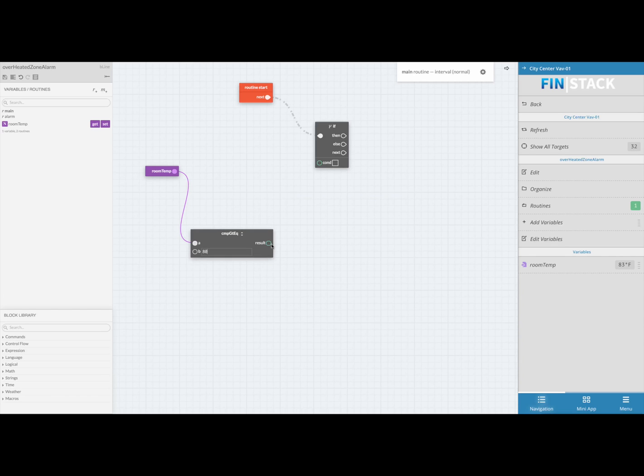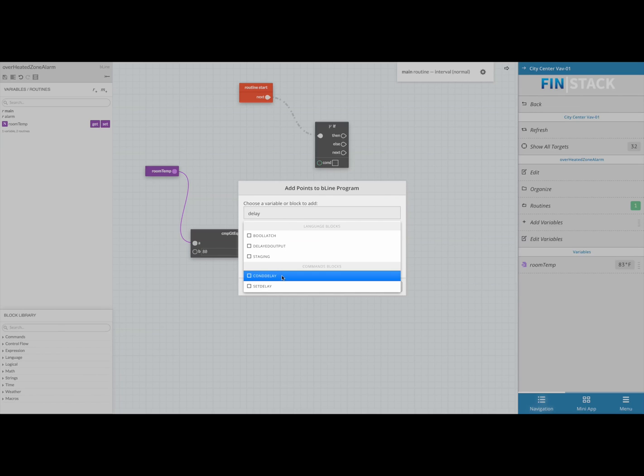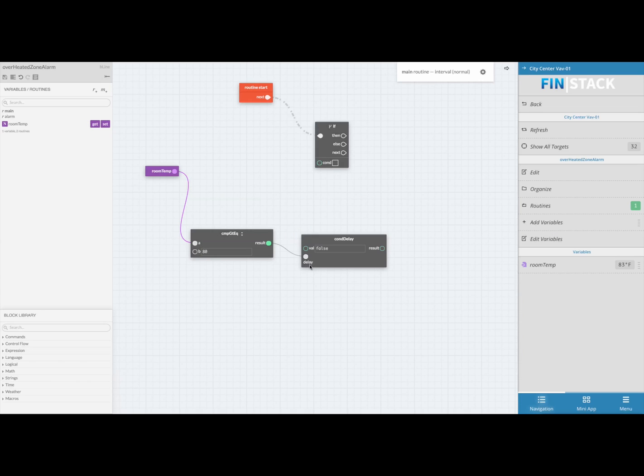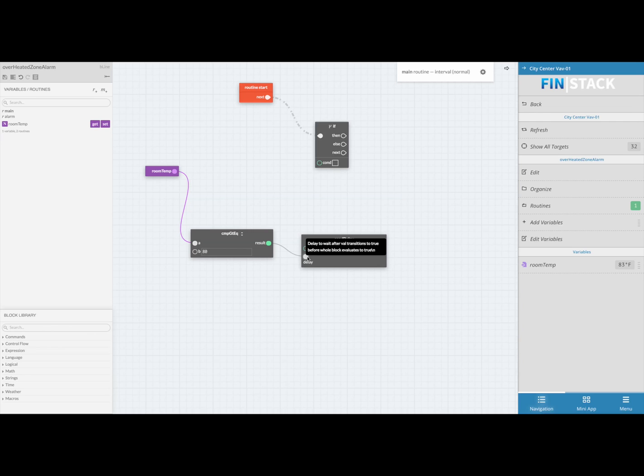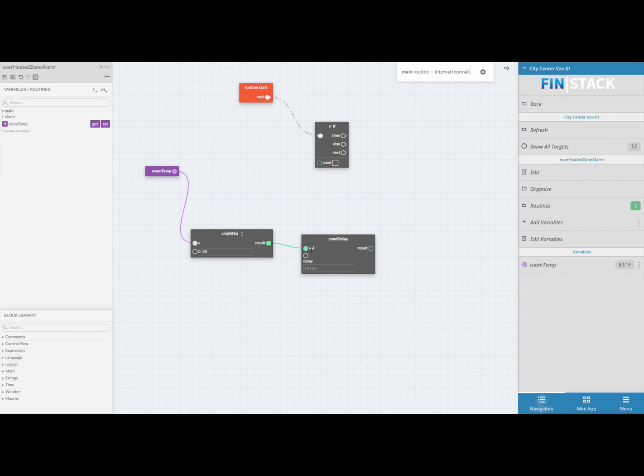I'm going to click on the greater than block's result bubble and create a link to a delay block. As soon as the delay block was added, you can see that by default it was linked to the delay property of the block, which in this scenario is not what I need. To delete a link, all you have to do is right click on the property and a tooltip will come up asking which link you would like to delete. Go ahead and delete the delay link and relink it to the correct slot, which in this case is the value. Once that's done, go ahead and type in a delay time, which in this case I'm just going to do five seconds for the sake of this video.